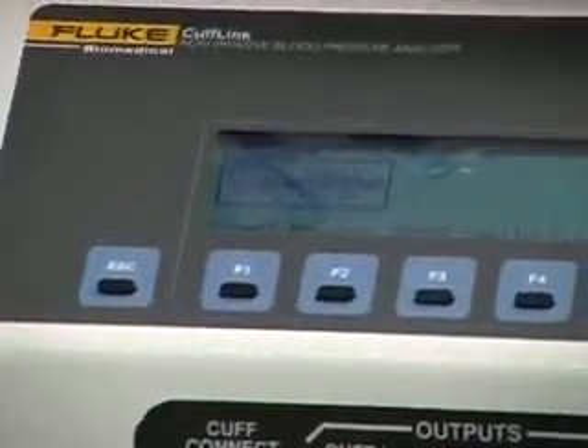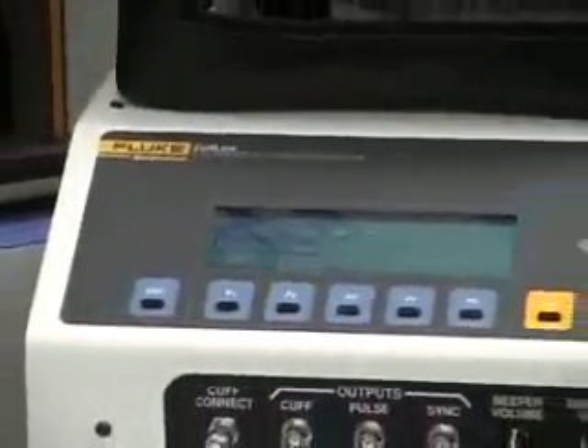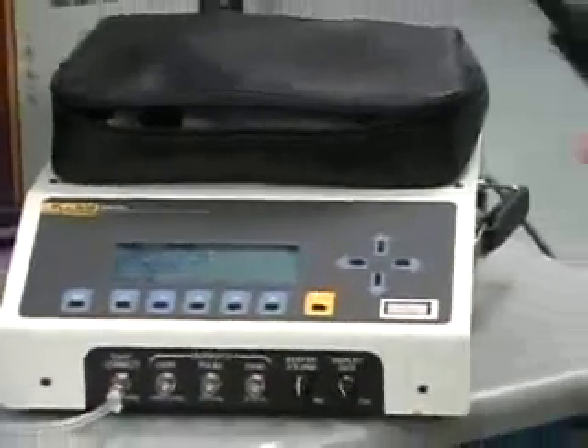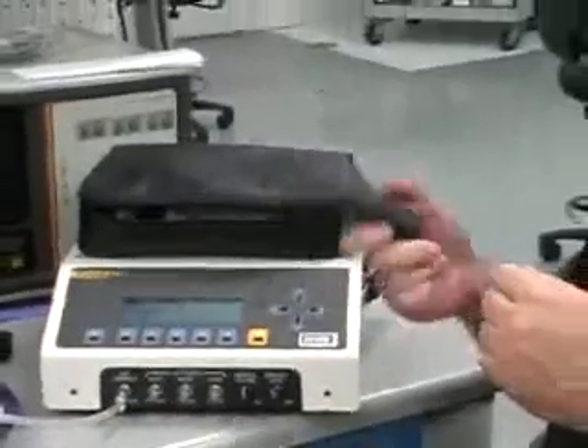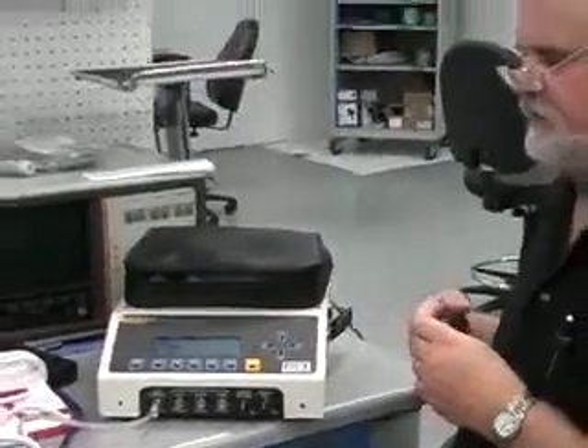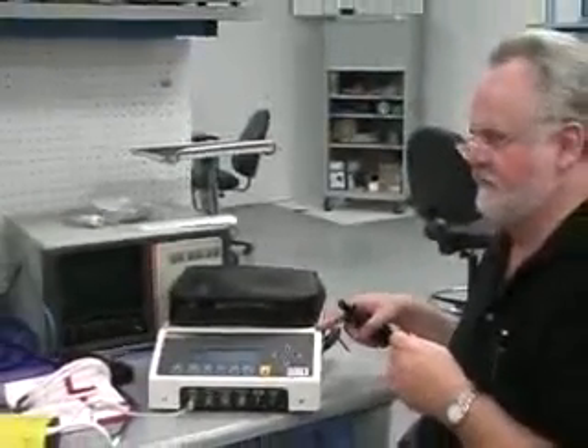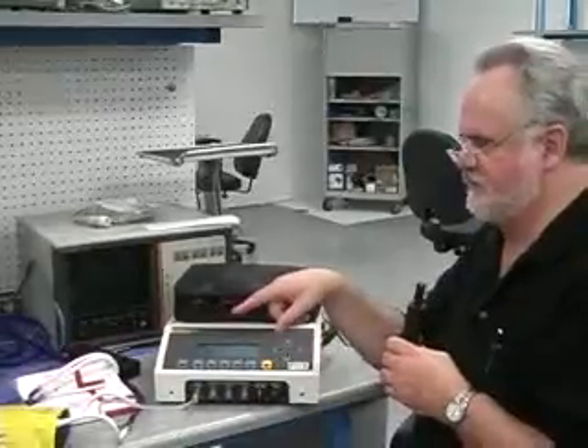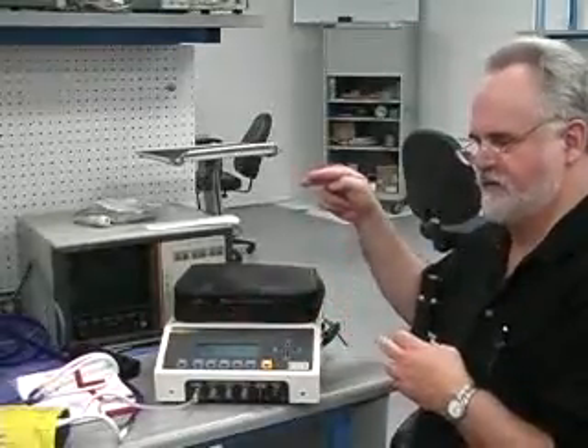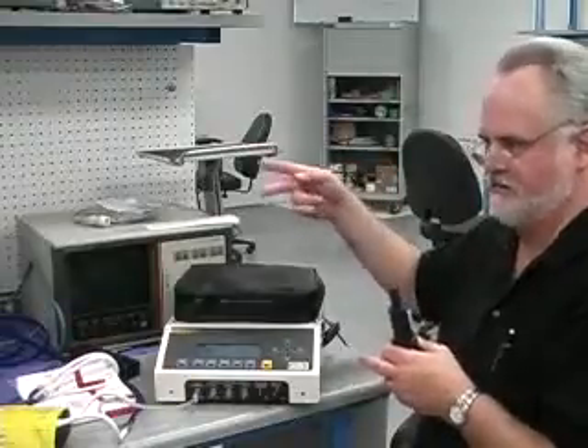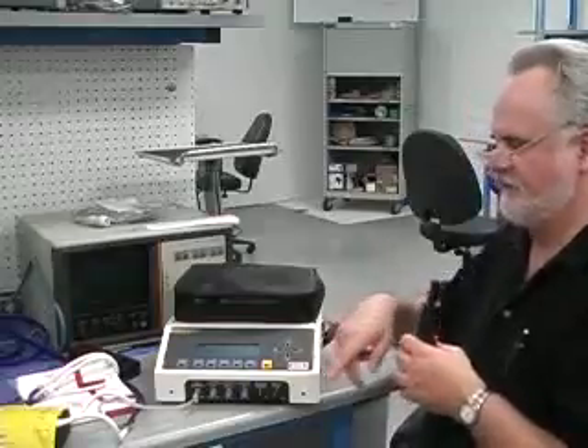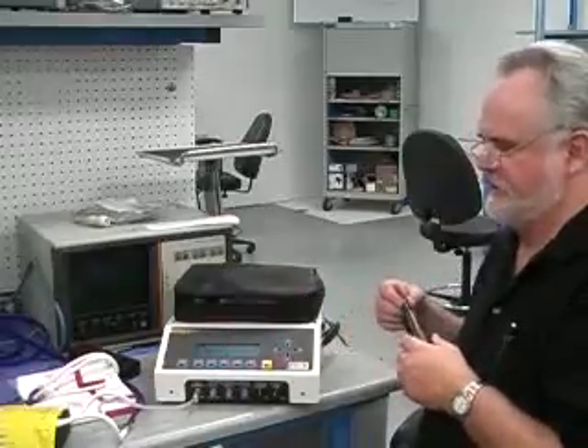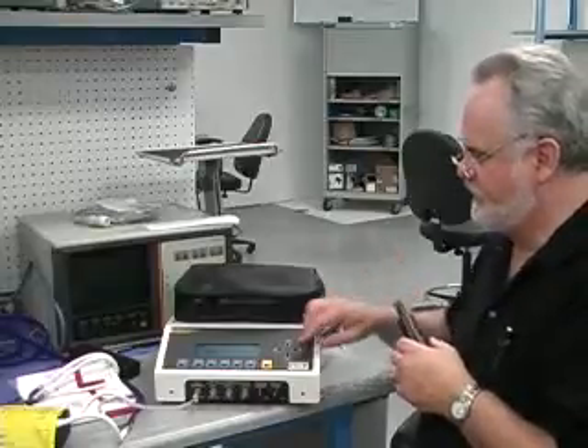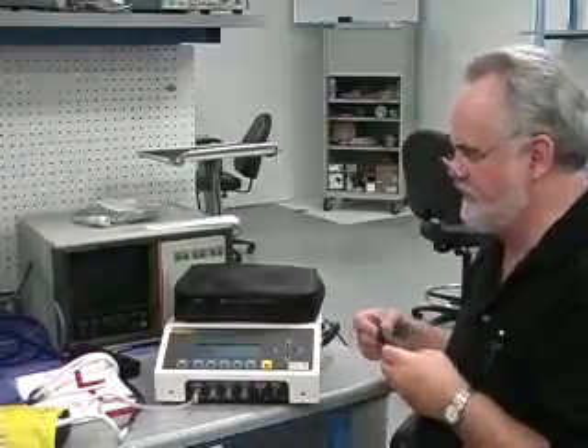So then it's basically the pulses are much narrower, and they're about 12% of the total adult amplitude. So very, very small pulses. As we can adjust the pulse amplitude in the adult, we can also do it in the neonatal. I guess since this is a fixed volume pulse, if you do use the larger cuffs, you can increase the amplitude of the pulse to make it approximately the same relative amplitude as when it would be coming out of the standard adult cuff-equipped system. We also do have an arrhythmia mode. That's an adult arrhythmia mode.